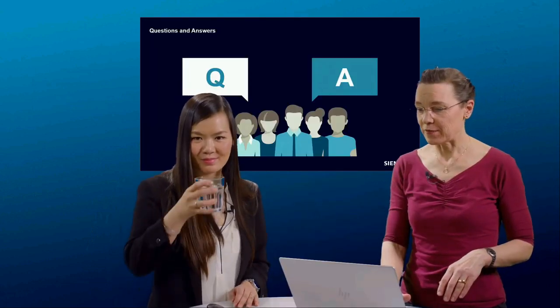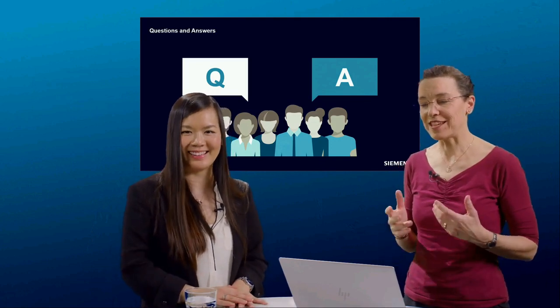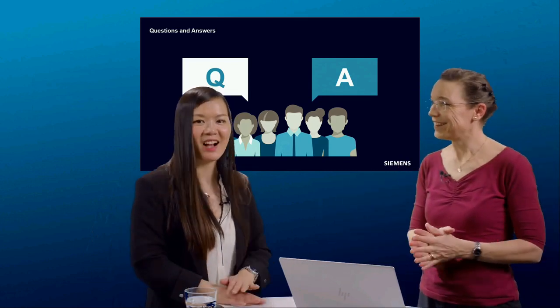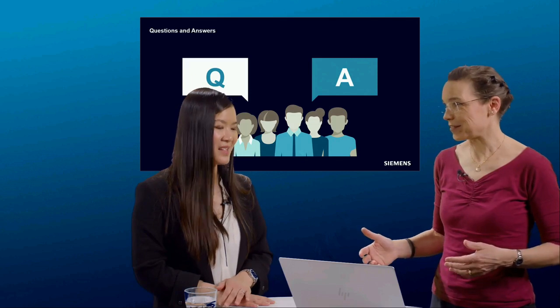Thanks for that. The next question is in the same direction. We have it twice: what is the best, vacuum or SF6, for this kind of application? From what I hear at exhibitions, get rid of SF6, but from a technical perspective, I can only say that whether SF6, vacuum, oil or whatever circuit breaker or GCB, we all have to pass the type tests mentioned by the standards. At the end, it's the customer who decides which advantages he wants with which solution. But our vacuum products fulfill the same standard requirements as our colleagues' SF6 products. Okay, so no matter what the insulation gas is, the type test is successfully performed.